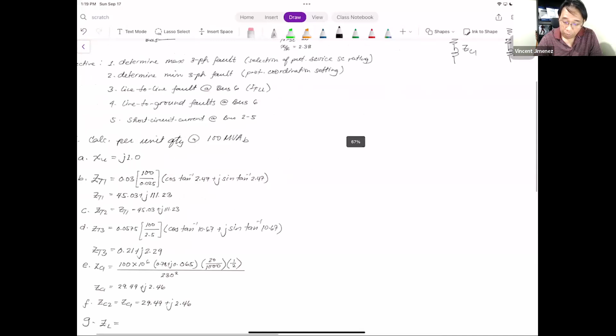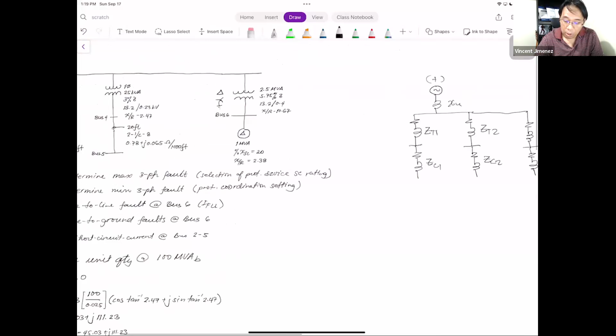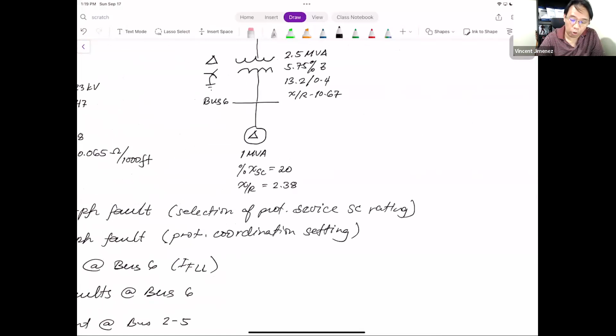We'll go now to the ZL, yung contributing load natin sa short circuit. ZL is equal to, given, what's given? 20% short circuit impedance, 1 MVA base, and X over R 2.38. So we need to convert this to 100 MVA base na select natin. So we have here 20%, that's 0.2, times power base new 100, power base old is 1 MVA.